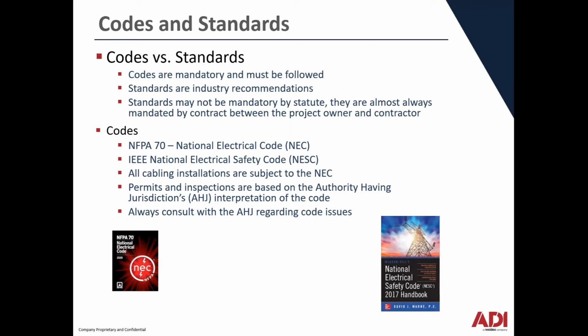The National Electrical Code dictates things like plenum versus non-plenum cable, how much voltage can go in a particular raceway system, and similar rules. It's enforceable by law through your local authority having jurisdiction, whereas standards are more industry recommendations. However, many standards bodies have done a good job bringing their standards into the architect and engineer world, where the engineer on a project will mandate compliance with particular standards - making it part of the contract that you must abide by.